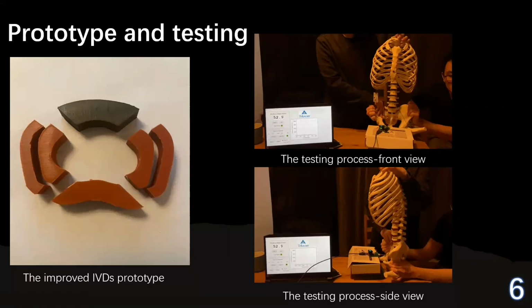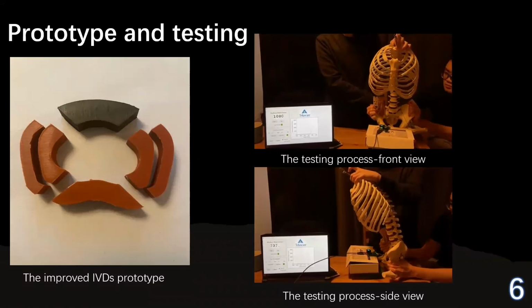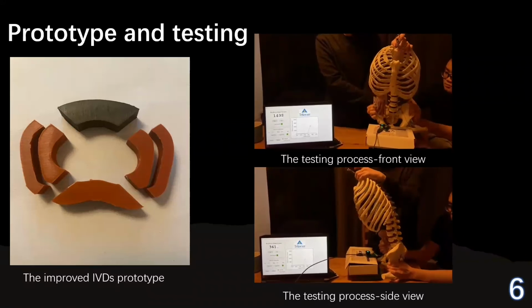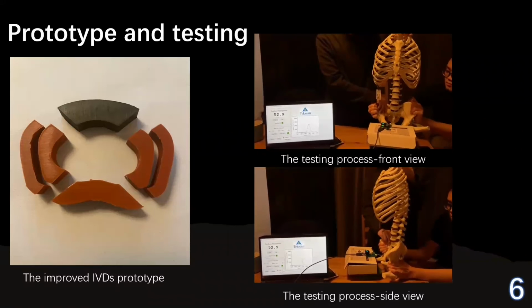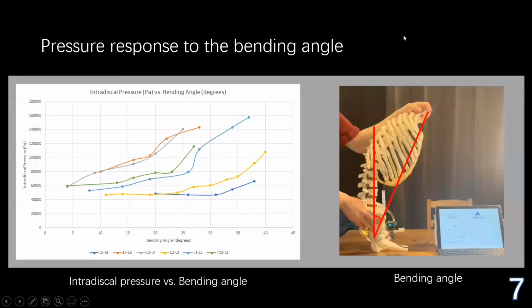The picture on the left is the prototype of the artificial IVD. Not only did we make a prototype of the artificial IVD, but we also integrated the artificial IVD and our sensing system into the actual model. These 2 videos on the right show the behavior of the model and the IVD pressure measurement when the spine was bent. With the working prototype, we successfully measured the pressure change of each IVD in the lumbar region.